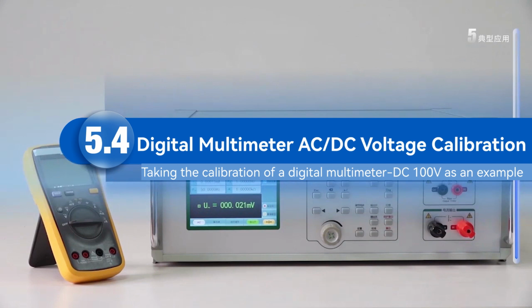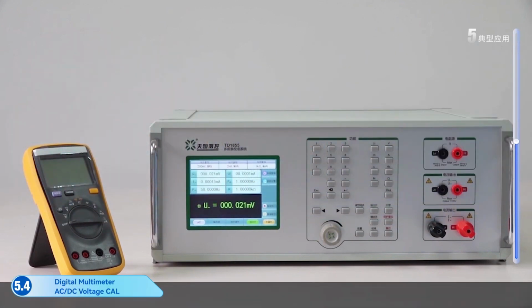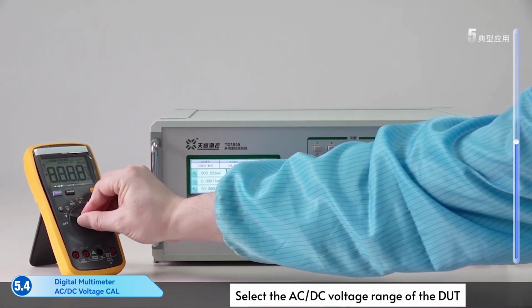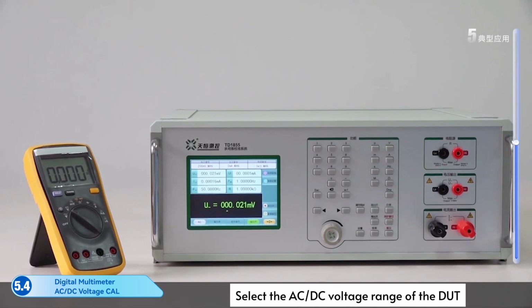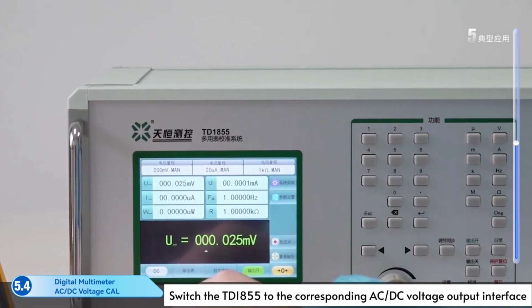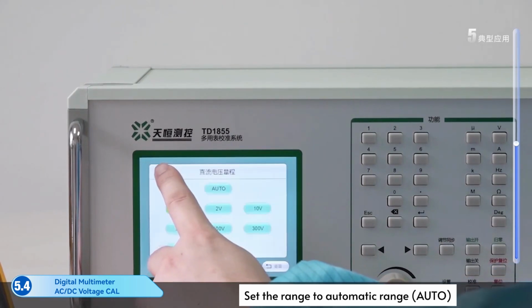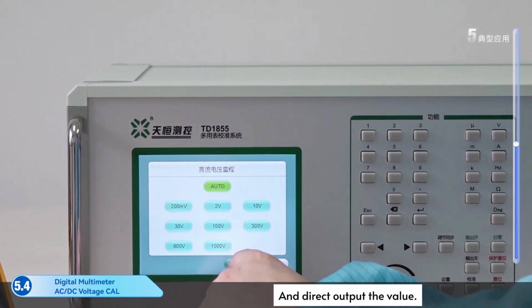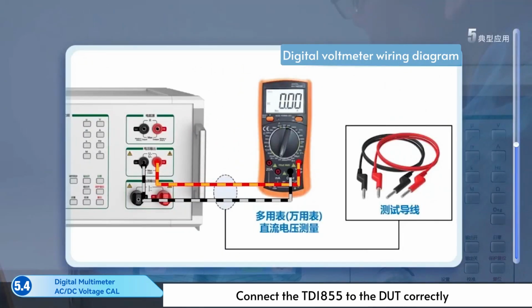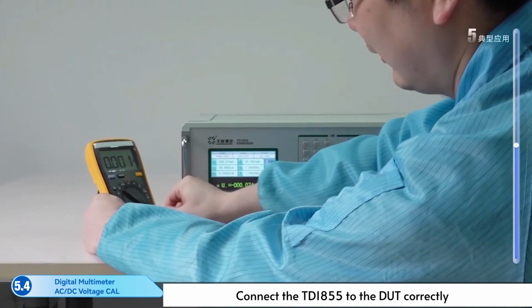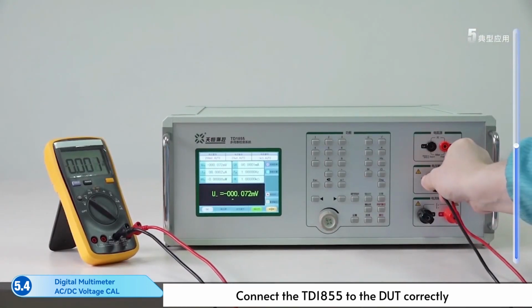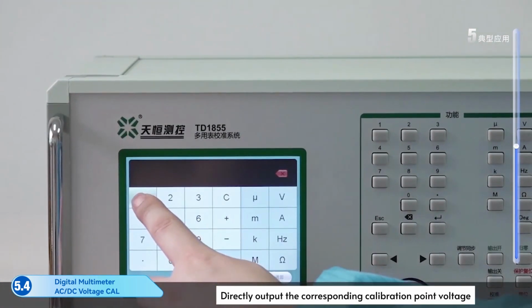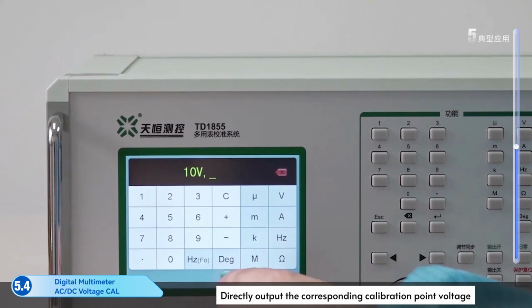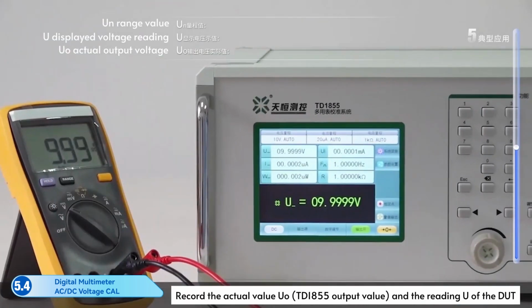Part 4. Digital Multimeter AC/DC Voltage Calibration. Select the AC/DC voltage range of the DUT. Switch the TD1855 to the corresponding AC/DC voltage output. Set the range to automatic range, and direct output the value. Connect the TD1855 to the DUT correctly. Directly output the corresponding calibration point voltage. Record the actual value and the reading of the DUT.